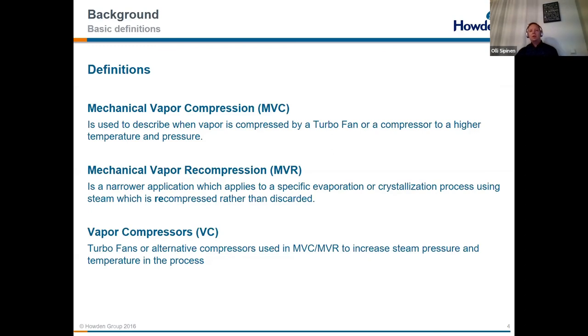Then I have just a few definitions which you will see through my presentation, and also in the previous ones. We talk about MVC, when we are lifting steam pressures to some target pressure and then continuing further in the process. And then we talk about MVR, which is a recompression, so we are circulating the same steam in the system, and we have vapor compressors to pressurize and lift the temperature. Underneath this compressor there are different technologies for how to make it happen.